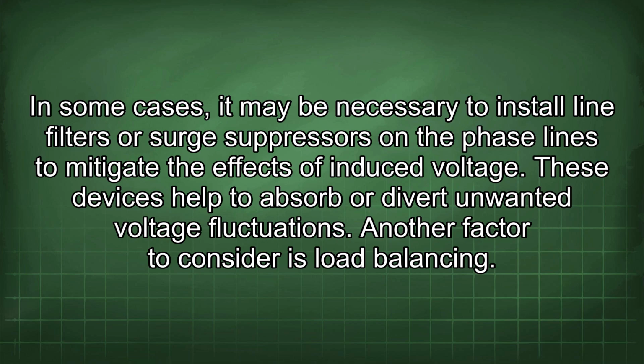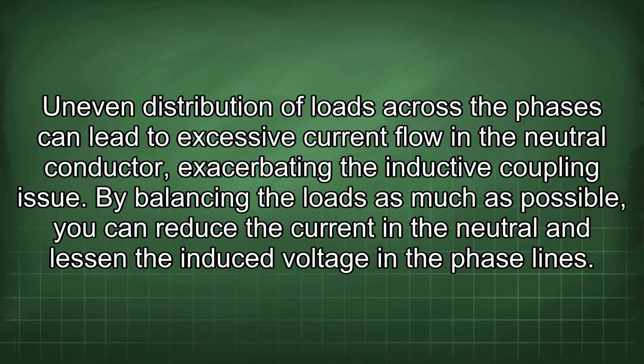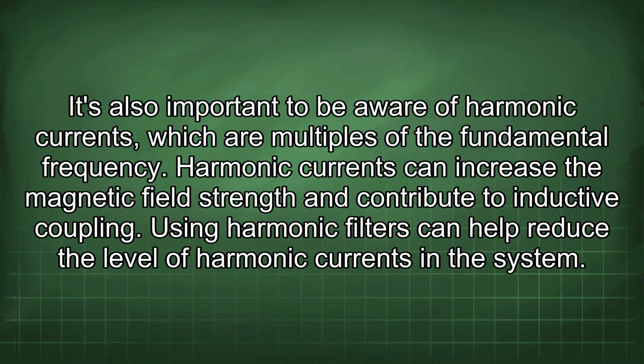Another factor to consider is load balancing. Uneven distribution of loads across the phases can lead to excessive current flow in the neutral conductor, exacerbating the inductive coupling issue. By balancing the loads as much as possible, you can reduce the current in the neutral and lessen the induced voltage in the phase lines. It's also important to be aware of harmonic currents, which are multiples of the fundamental frequency. Harmonic currents can increase the magnetic field strength and contribute to inductive coupling. Using harmonic filters can help reduce the level of harmonic currents in the system.